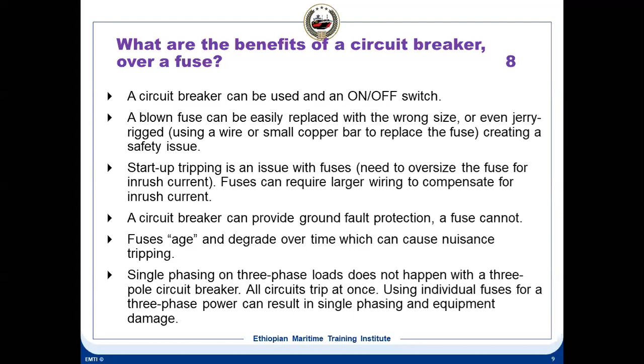You see, in a breaker, once the breaker trips, it opens the three contacts altogether. But if you have three fuses for a three-phase supply, if one fuse blows off, it becomes a single phasing. So this is one dangerous situation. Whenever you use a three-phase supply, if one fuse blows, it becomes single phasing. In case of a breaker, it doesn't happen. It trips all the three phases.